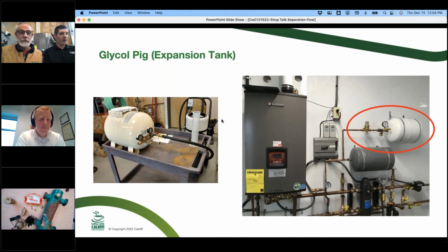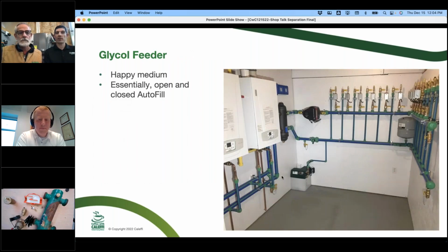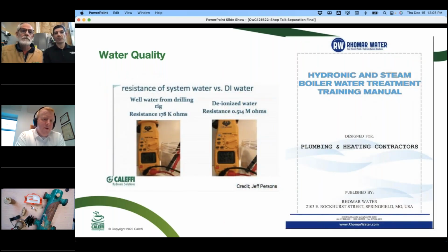So one thing before we get to that point, and we have another video about this on Shop Talk, but one compromise that I think Cody and I would probably have would be a glycol feeder. So let's say you do need that extra gulp of glycol that's already pre-mixed to exactly what you want, 50/50 blue or whatever. Instead of filling from the street forever, you can just pull a cup of that fluid out of the glycol feeder, and that's a good way to go, because you can go back a week or a month or a year from then and see, okay, we filled a full gallon, or this thing is dry, we need to find a leak, but it's not an emergency callback on New Year's Eve or something like that.